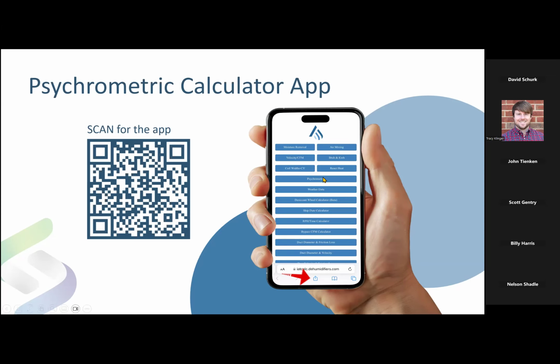You can do psychrometric state points. You can get weather data for all the ASHRAE weather stations in the US, Canada, and Mexico. You can do mixed air calculations. And once you're up to speed, you can actually select a desiccant wheel yourself. I use this 10 times a day. Every job I do, I'm either pulling it out on my phone or pulling it up on my laptop. It's great for making engineering calculations, and that's our gift to you, if you will.